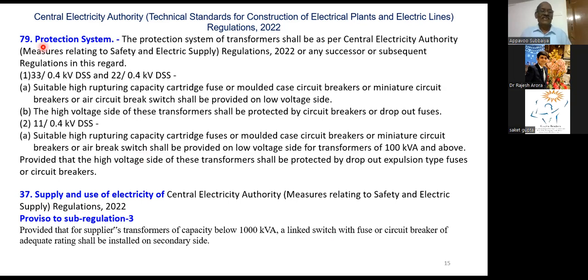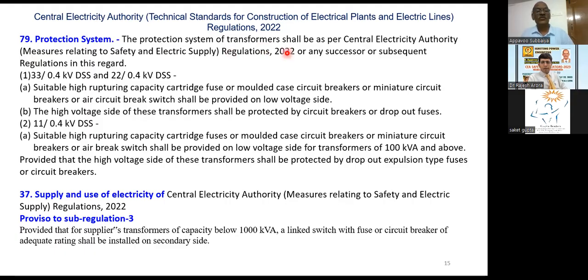Okay, so this is a protection system where it is stipulated that you have to observe the CEA Measures Relating to Safety and Electric Supply 2022. What this regulation 79 specifically provides is that you have to provide HRC cartridge fuses. These are things for the HT side and the LT side. What are the provisions you have to make to protect the lines? There is one more provision as per 37. This is our CEA regulation 2022.